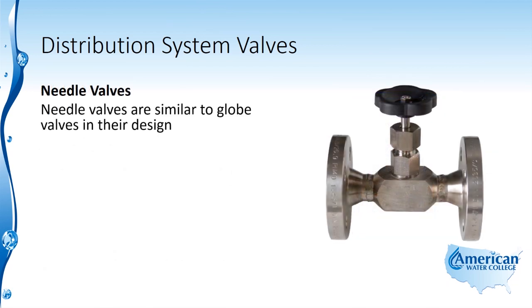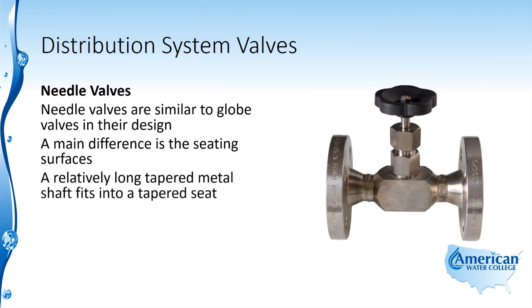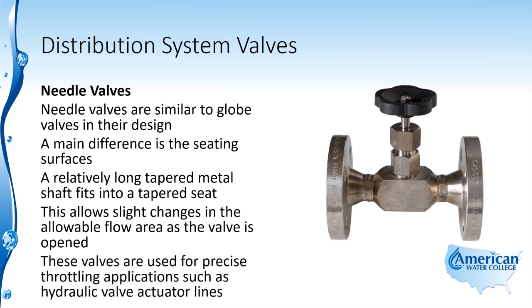Needle valves are similar to globe valves in their design. The main difference is the seating surfaces — a relatively long tapered metal shaft fits into a tapered seat, which allows slight changes in the allowable flow area as the valve is opened. These valves are used for precise throttling applications such as hydraulic valve actuator lines.